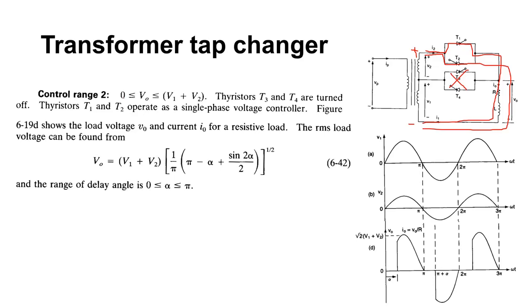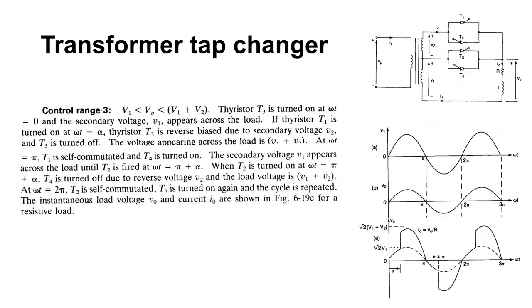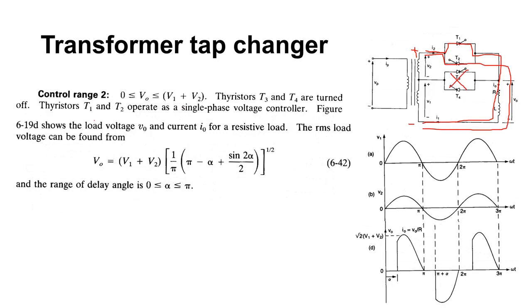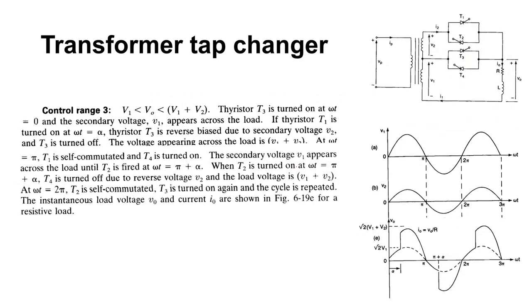If you look at it here, control range 2 is from 0 to V1 plus V2, and control range 3 is from V1 to V1 plus V2. That means this part can also be done by only controlling the firing angle alpha. However, if you have different tap settings, then you can take advantage of both of these thyristors, both of these two branches here.